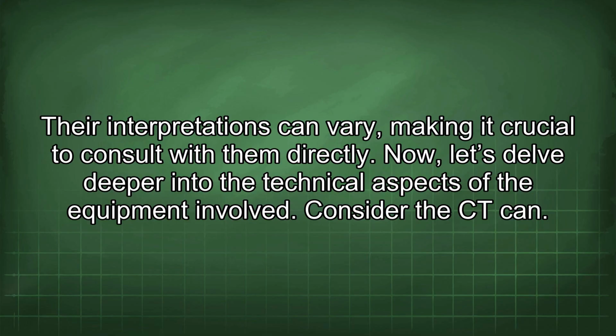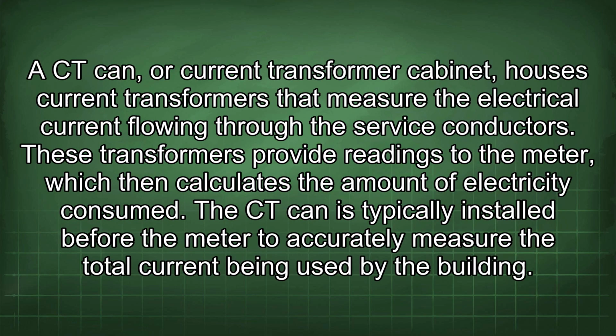Consider the CT can. A CT can, or current transformer cabinet, houses current transformers that measure the electrical current flowing through the service conductors. These transformers provide readings to the meter, which then calculates the amount of electricity consumed. The CT can is typically installed before the meter to accurately measure the total current being used by the building.